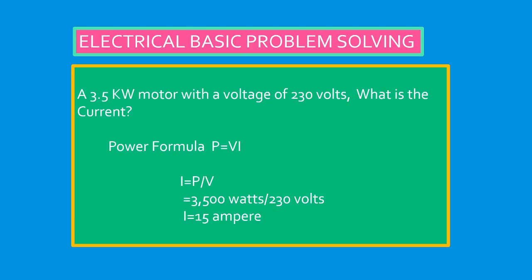Here is an application of the formulas discussed. Example: a 3.5 kilowatt motor with a voltage of 230 volts — what is the current? Power formula: P = V × I, so I = P ÷ V. Since 1 kW = 1,000 W, P = 3,500 watts. Therefore I = 3,500 ÷ 230 = approximately 15 amperes.